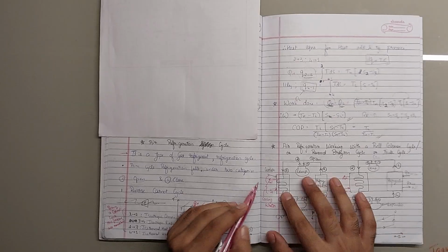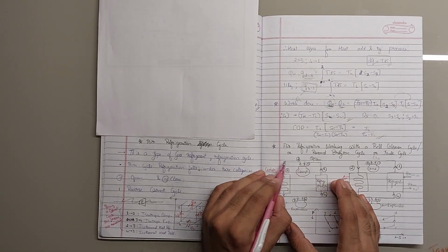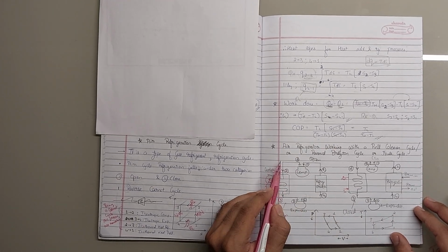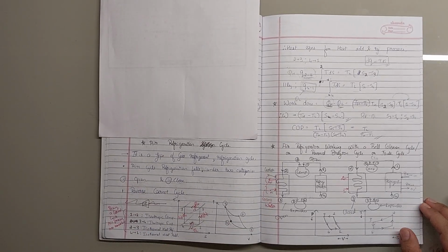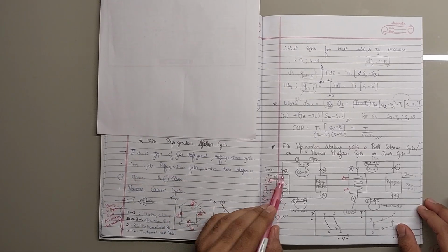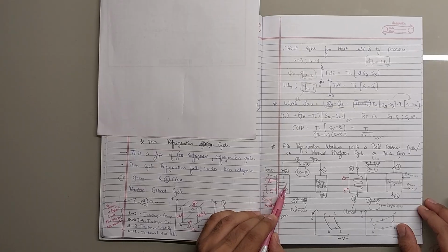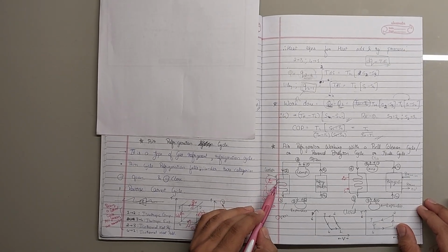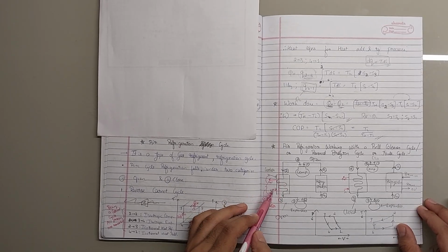In 2 to 3 what happens is, we have a cooling water system. This is the hot compressed air at point 2. The compressed air from point 2 enters the cooler. It can be imagined as a shell and tube type heat exchanger assembly, wherein the hot air passes through the tube, and in the background, in the shell, cold water is flowing.